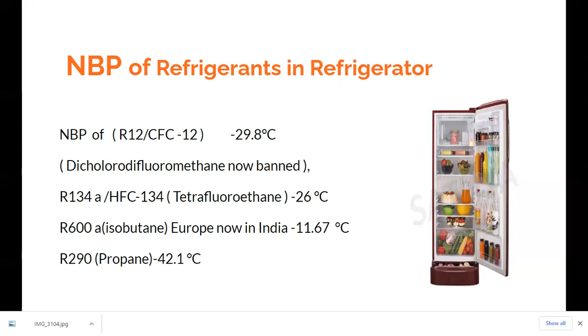Some advanced countries like those in Europe use hydrocarbons as a refrigerant. Even in India now, hydrocarbons are being used as a refrigerant in refrigerators, in small quantity. They also have a negative normal boiling point. For example, isobutane R600A has a normal boiling point of minus 11.67, which is much below the atmospheric temperature. Similarly, propane R290 has a normal boiling point of minus 42.1 degrees centigrade. So all the refrigerants used in refrigerators have a negative normal boiling point, closer to minus 29.8 degrees centigrade, which was the normal boiling point of the conventional refrigerant, which is now banned, that is CFC12.